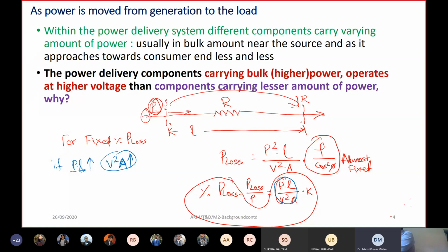So just correlate that what if we choose, say for example, voltage, then what should be the size of the conductor? Or if we choose the size of the conductor, then what should be the voltage? For fixed percentage of loss, the correlation for the size of the conductor A is equal to P L by V square and some constant, say K1.